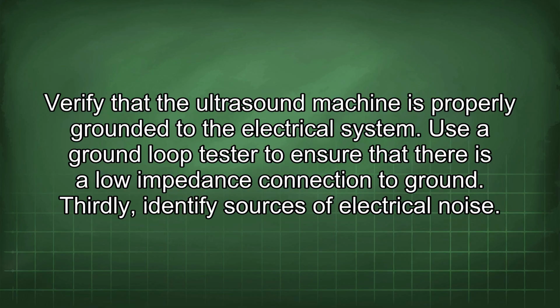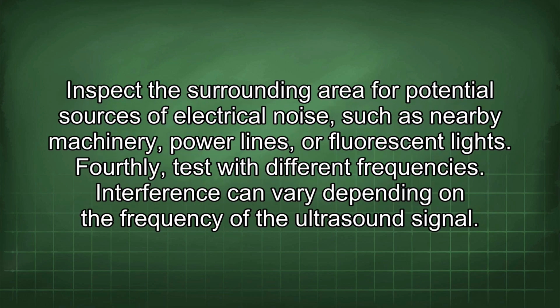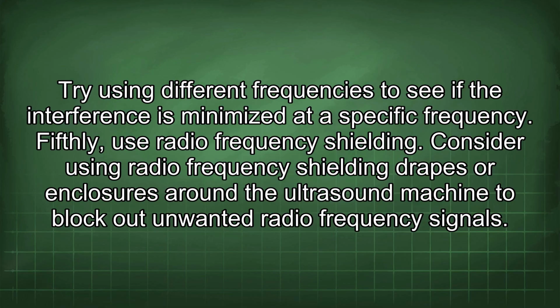Thirdly, identify sources of electrical noise. Inspect the surrounding area for potential sources of electrical noise, such as nearby machinery, power lines, or fluorescent lights. Fourthly, test with different frequencies. Interference can vary depending on the frequency of the ultrasound signal. Try using different frequencies to see if the interference is minimized at the specific frequency.